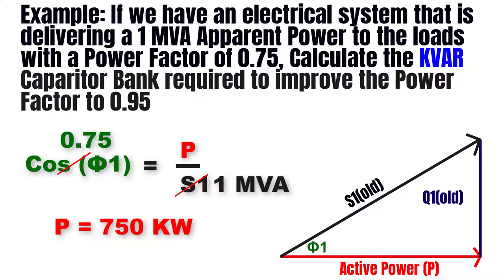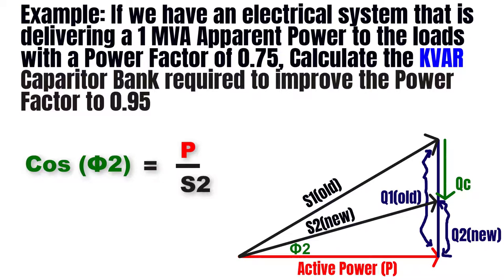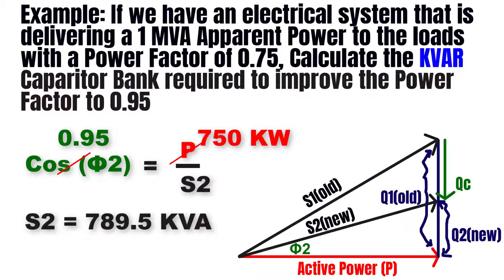We can observe that we have useful power of 750 kilowatts, but because the power factor is low, the total apparent power is much higher than the active power, which creates a burden on the system. After connecting a capacitor bank, the new power factor equals 0.95, so the new apparent power S2 equals 750 kW divided by 0.95, which equals 789.5 kVA — much closer to the active power value. We have now decreased the unuseful power and reduced the burden on the system.